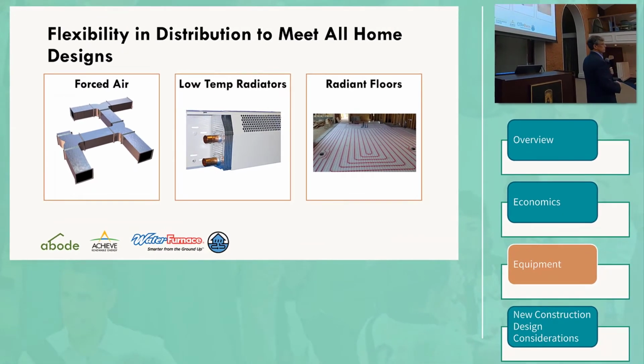Distribution by ducted systems is most common because we do heating and cooling that way. But it is possible to retrofit or install baseboard radiation. Typically, we try to put in baseboard that's designed for the lower fluid temperatures of the geothermal equipment. Other manufacturers' equipment tops out at about 125 or 130 degrees Fahrenheit, which is not close to a typical boiler temperature of 165 or 175. WaterFurnace has a product line that makes it up to 145, 150, so that's closer, but still lower than the boiler.